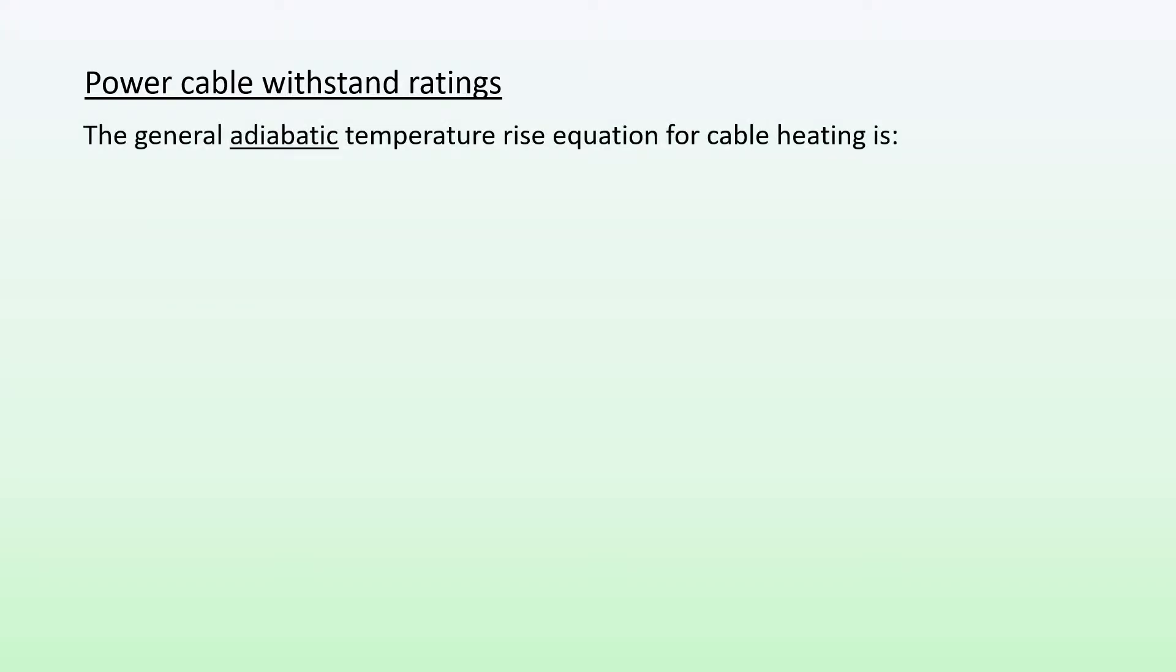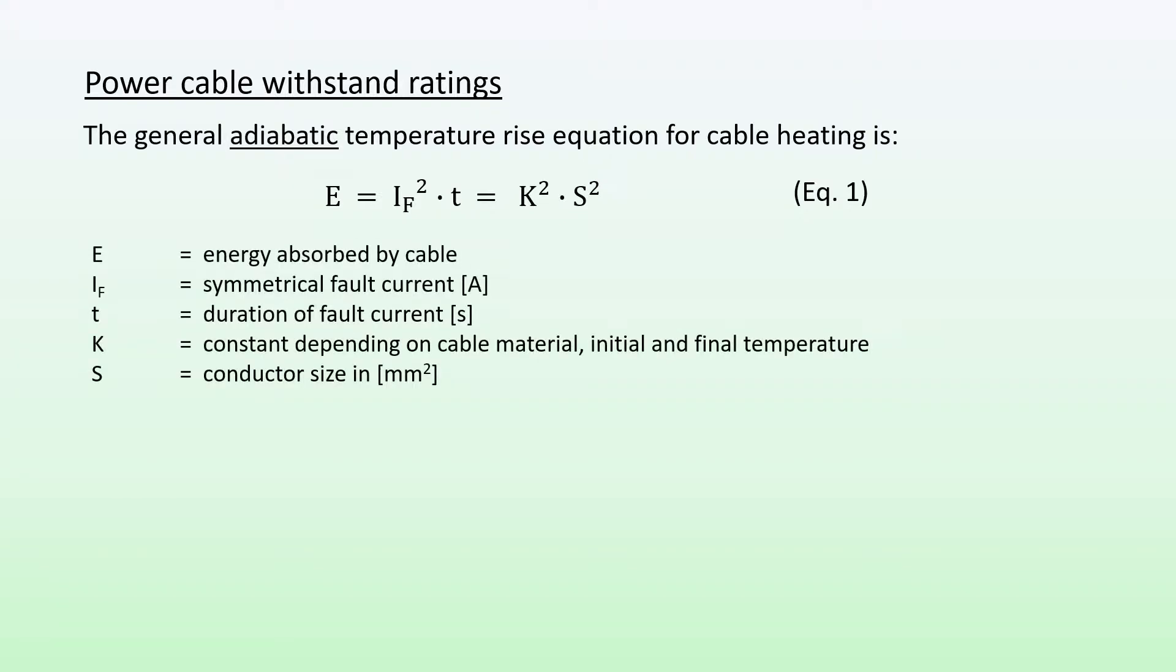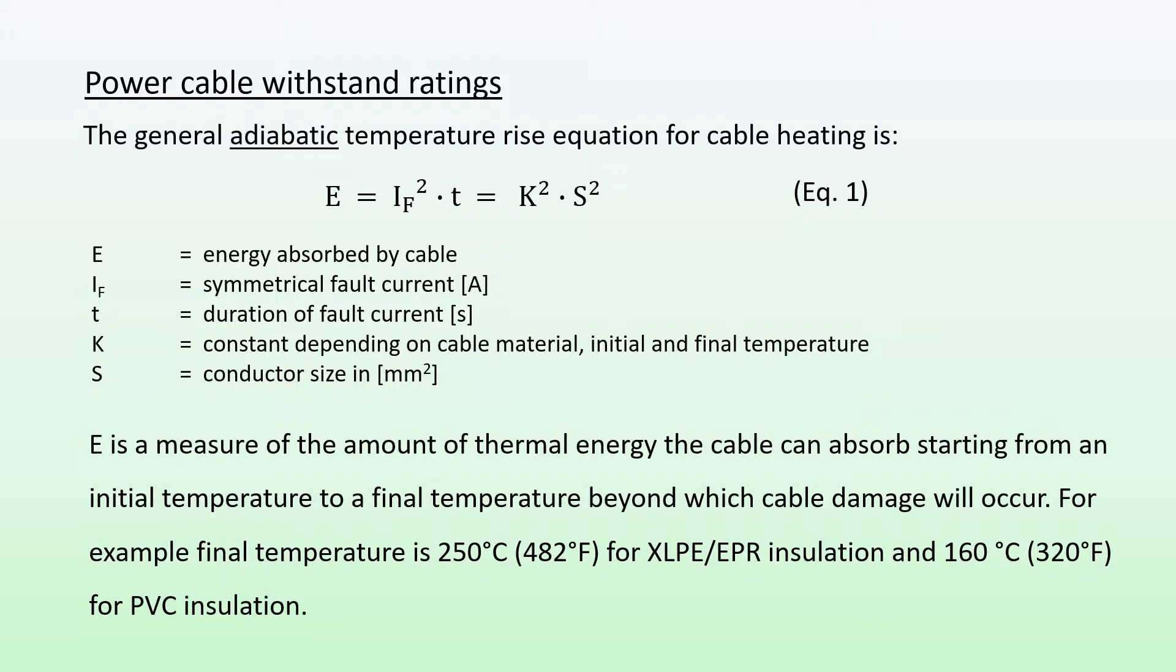The general adiabatic temperature rise equation for cable heating is as follows: E = I²·t = K²·S². What do these stand for? E is the energy absorbed by the cable during a fault situation, If is the symmetrical fault current, and t is the duration of fault current in seconds. K is a constant depending on cable material, the initial and final temperature. S is the conductor size in millimeters squared. So E is a measure of the amount of thermal energy the cable can absorb starting from an initial temperature to a final temperature, beyond which cable damage will occur.